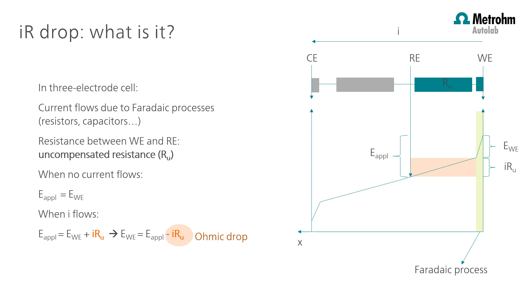What does the potentiostat need to do to compensate for this resistance? Basically, it applies a slightly higher potential between the working electrode and the reference electrode so that the actual potential at the working electrode is the one set point in the software. And this is called IR drop compensation.